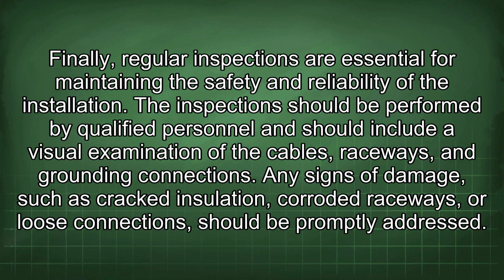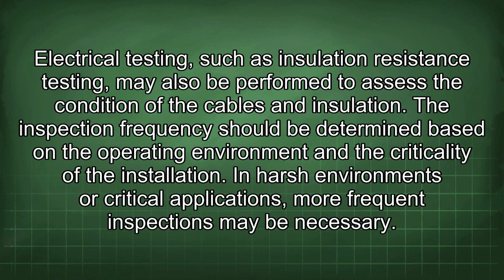The inspection should be performed by qualified personnel and should include a visual examination of the cables, raceways, and grounding connections. Any signs of damage, such as cracked insulation, corroded raceways, or loose connections, should be promptly addressed. Electrical testing, such as insulation resistance testing, may also be performed to assess the condition of the cables and insulation. The inspection frequency should be determined based on the operating environment and the criticality of the installation. In harsh environments or critical applications, more frequent inspections may be necessary.